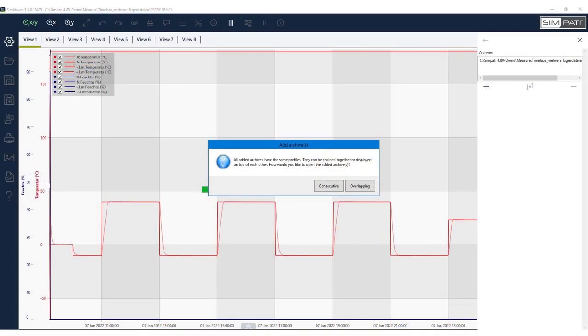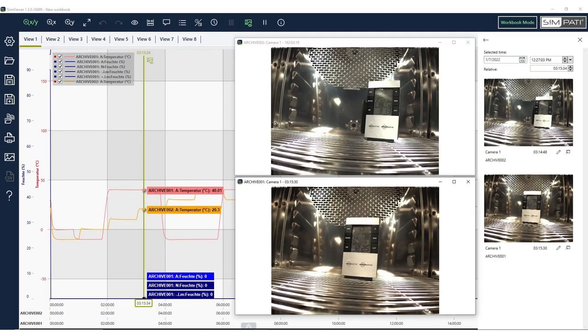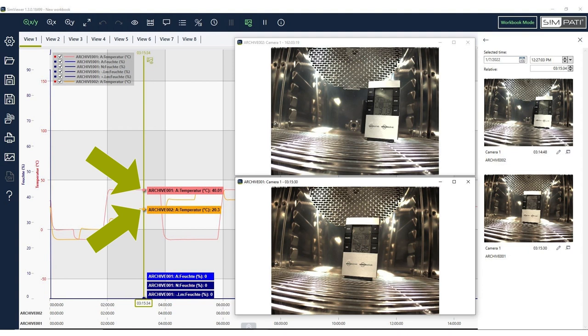As of Update 4.80 Patch 1, evaluations and image material from different test runs and chambers can be overlapped and compared. On a push of a button, you now overlap your reference graphs with a graph of your current test runs. This allows you to quickly and easily compare different archives for optimization of your test runs.